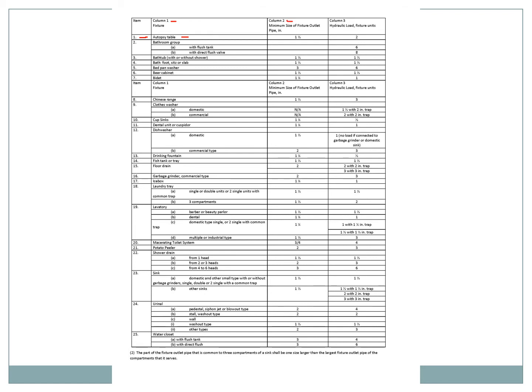Column number two is the minimum size of the fixture outlet pipe — it can't be any smaller than this. This is the one I use more often than anything. Unless you have specific instructions to upsize, you do not upsize. In this column, it's all in inches — so even though it only says one and a half, it means one and a half inch pipe size. It's important to remember that when you see the word 'size,' they're not talking about length or outside diameter — they're talking about nominal pipe size, which is approximately the inside diameter.